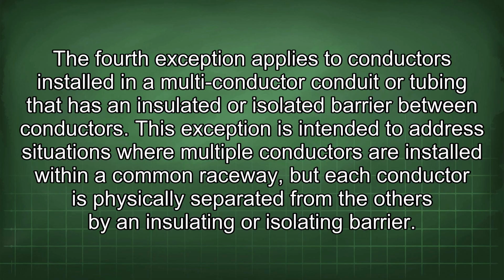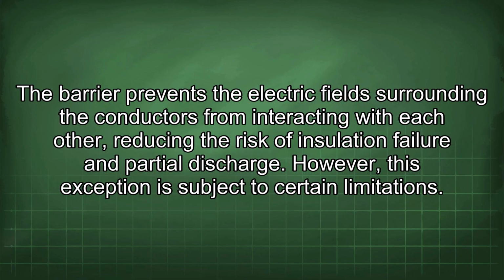This exception is intended to address situations where multiple conductors are installed within a common raceway, but each conductor is physically separated from the others by an insulating or isolating barrier. The barrier prevents the electric field surrounding the conductors from interacting with each other, reducing the risk of insulation failure and partial discharge. However, this exception is subject to certain limitations.